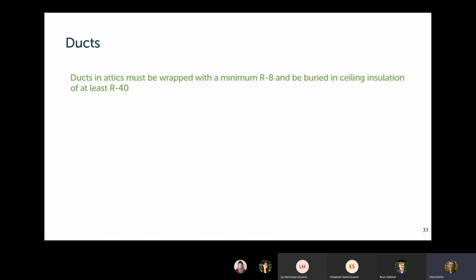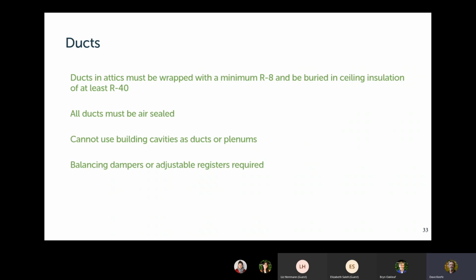Also, requirements on ducts. If you run your ducts through the attic or through any other unconditioned space, they have to be wrapped with a minimum R8, and they have to be buried in ceiling insulation of at least R40. This is a lot of insulation. And note that unless you're smart about where you put them, and you put them right down low on the ceiling to begin with, it's really hard to bury them in ceiling insulation of at least R40. That's a foot on top of the ducts. And in addition, all ducts must be air sealed, whether they're inside the house or outside the house. The idea is that some attempt should be made to make them airtight. You can't use building cavities as ducts or plenums. You need balancing dampers or some sort of adjustable register so that the system can be balanced on a room-to-room basis.